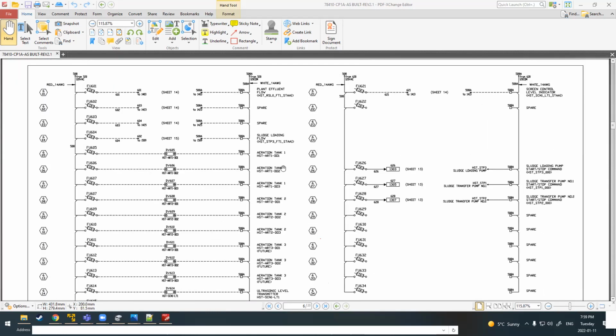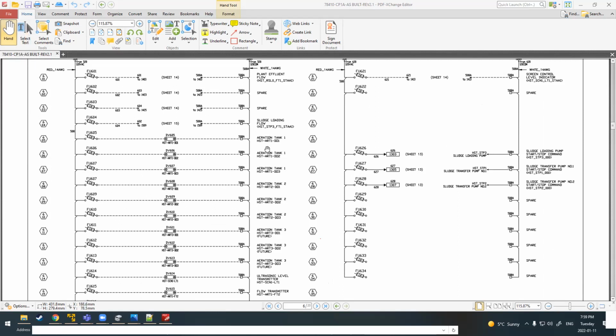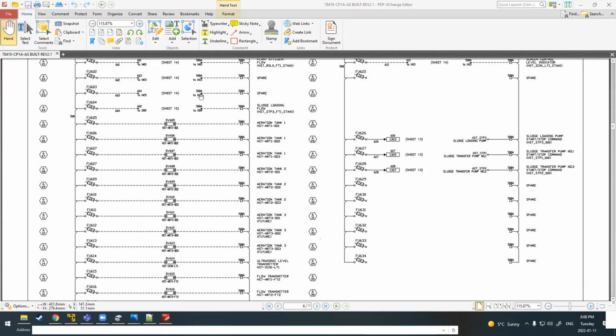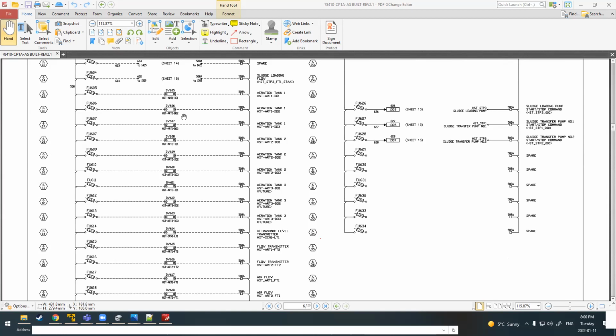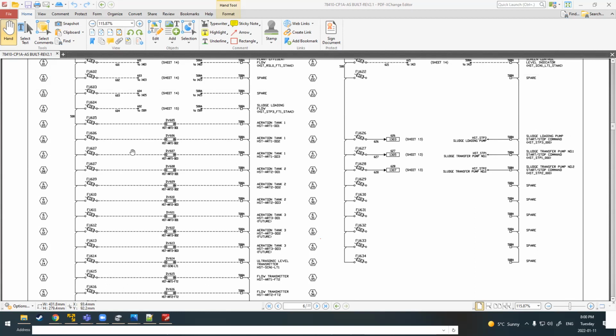The next drawing here, again, we're back to 120. It looks like it's all fusing now, no more circuit breakers. And this says plant effluent flow. So that's a flow meter. Aeration tank, DO. That stands for dissolved oxygen. This is, again, specific to wastewater. So these different devices are just being powered by 120 again.